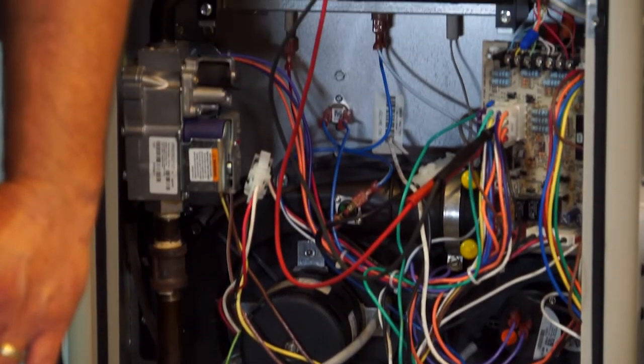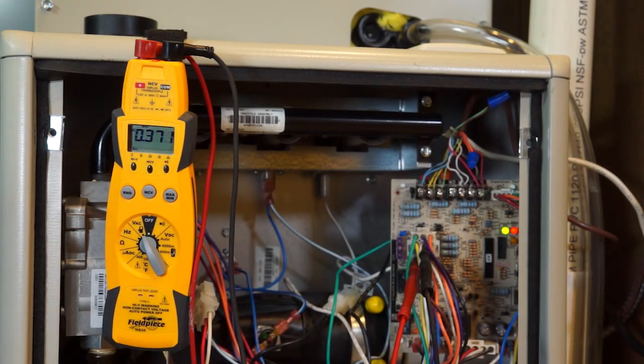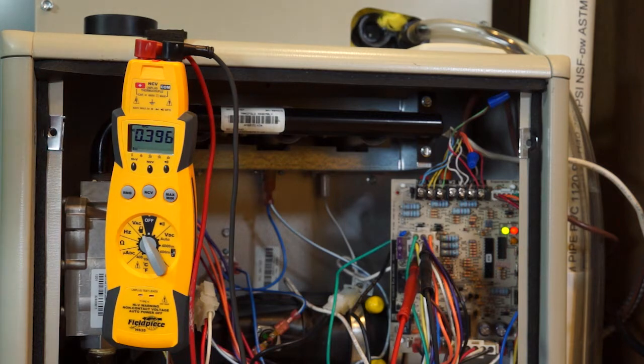So without further ado, we're going to move on and I'm going to show you what it does when you have high resistance in it. Okay, so here we go. The furnace is starting its ignition cycle. The inducer is starting and after we finish our pre-purge with the inducer running, then we should see the igniter start to glow. And that should be happening here in just a second.